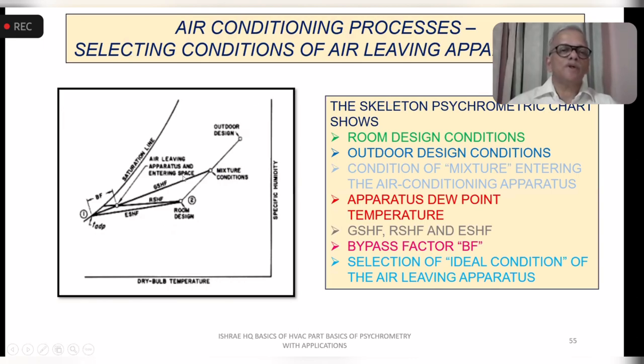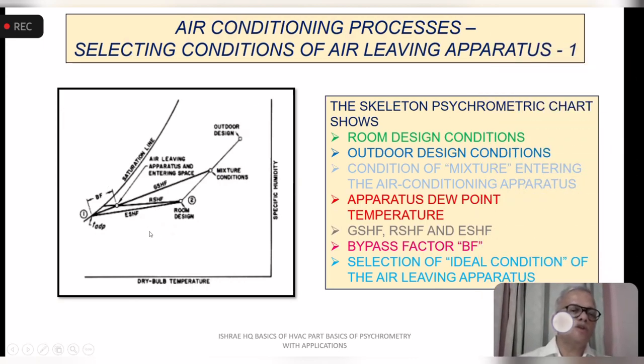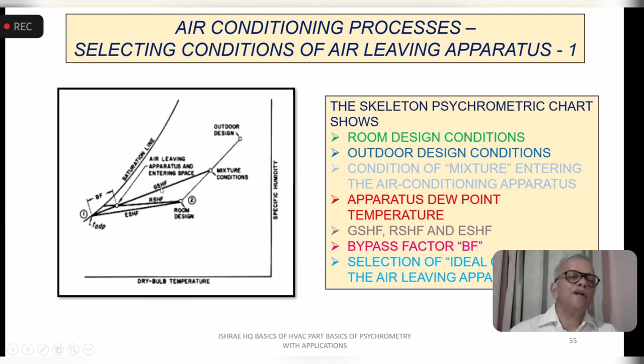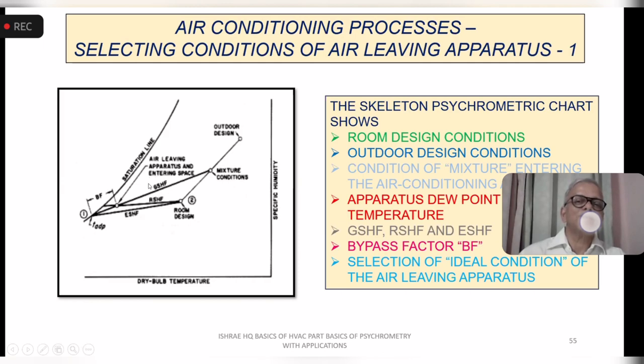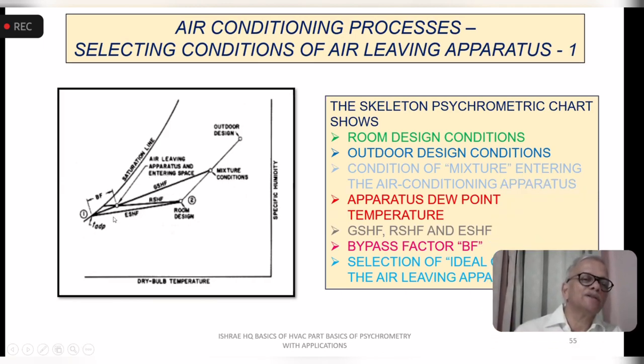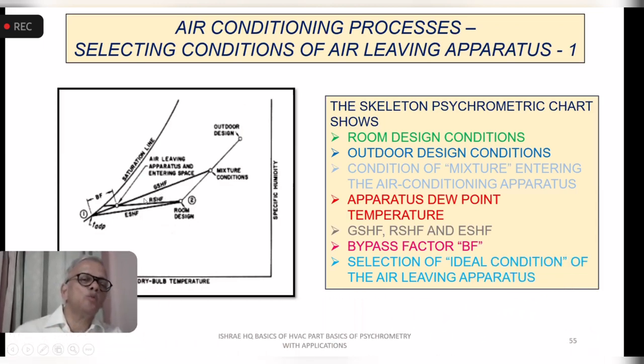Now, this is the same skeleton chart. Here you will find three different sensible heat factors. One is the grand sensible heat factor, one is the effective sensible heat factor, and one is the room sensible heat factor. All of them have different slopes and different starting points. So this line is passing through the room design because it is the room sensible heat factor and the effective room sensible heat factor.